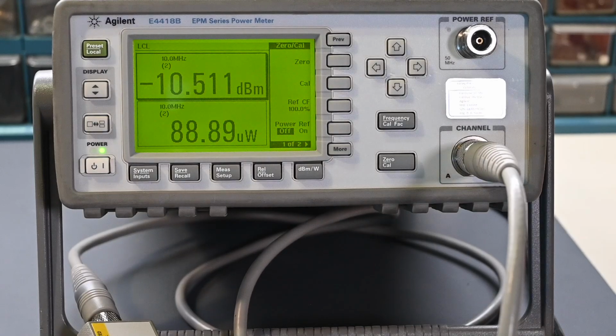So to do the testing and calibration on the spectrum analyzer, I need to have an RF signal that has a very stable amplitude and frequency. So we have to allow for the loss that's in the cable between the signal generator and the spectrum analyzer's input, because it is a measurable loss. So right now you can see on the display it says minus 10.5 dBm, basically 10.511, so about 10.5 dBm. Well, the signal generator is set to minus 10 dBm, so there's about a half dB loss in the cable, and that's reasonable, it makes sense.